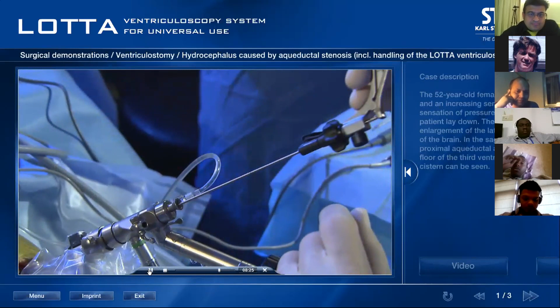All the instruments feature a length marking which shows when the tip of the instrument emerges from the working channel. Now what we have done is, the length of the instrument is usually 30 centimeter. When a surgeon is putting the instrument in, first of all, we have given you a funnel shape, because when you try to aim your instrument, if this opening is small and not funnel shaped, then the instrument is dangling here and there, some are semi-rigid. So the surgeon has to keep looking when his instrument is going to be out in the ventricle through the neuroendoscope sheath, because you are seeing in 2D. The endoscopic image is a 2D image on the monitor.